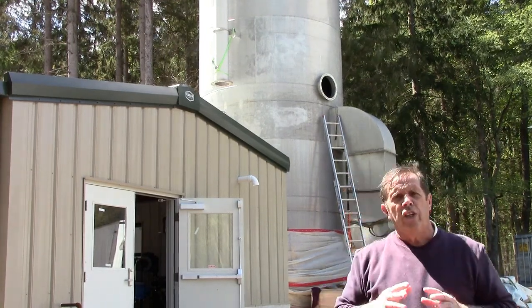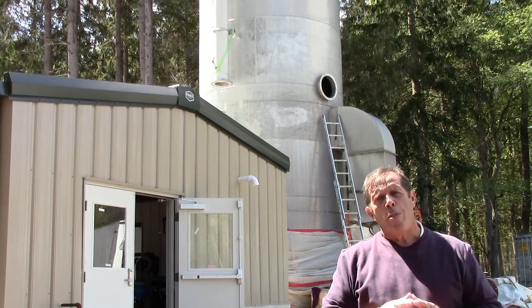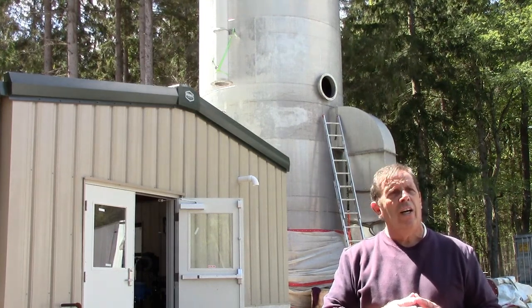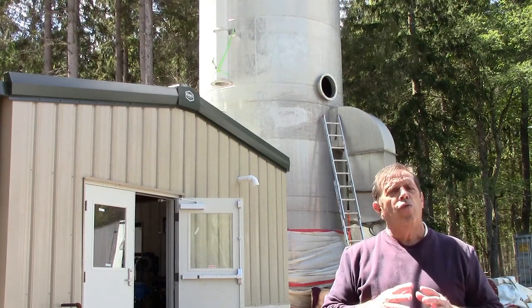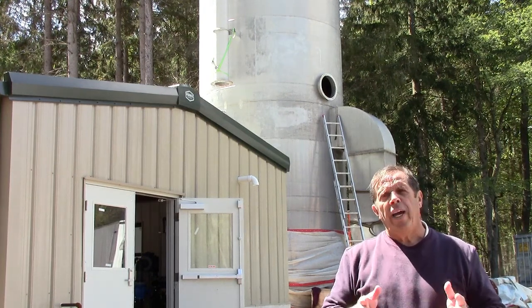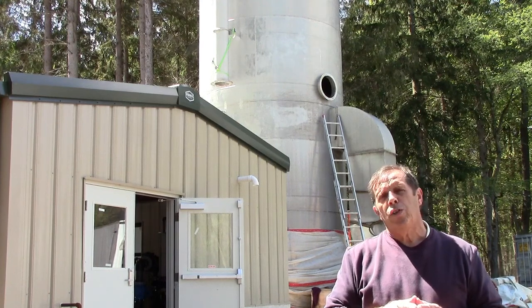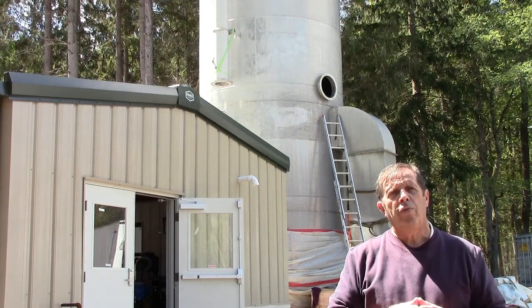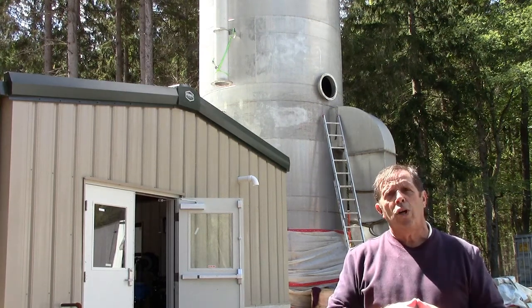Collectively, here for the City of Cortland, we have the capacity of about 15 million gallons a day. We're well below that. We do about 2.5 million gallons a day, pretty much every day, with the college in session and all that. So it's a very strong aquifer with very high capacity pumping, and we have pretty much 5 million gallons of water in storage. If for some reason we can't pump, we've got a 2-day supply in storage. So we're very resilient to most anything that could slow down our water production.